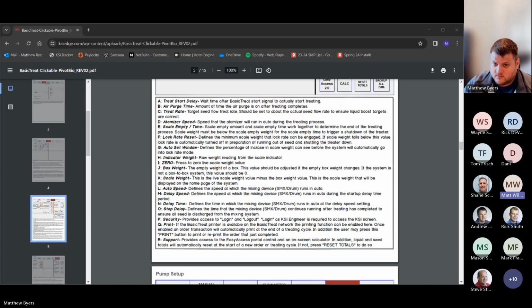It was just about how wind, when treating outdoors, affects the additive feeder's weight calibration, I guess is the best way to put it. So, the unit in question is using a USC dry additive feeder that's got a load cell on it. The KSi one does not have a load cell, so that dry additive feeder should not suffer from that issue on a KSi unit. Okay, very good, that's the question I had.